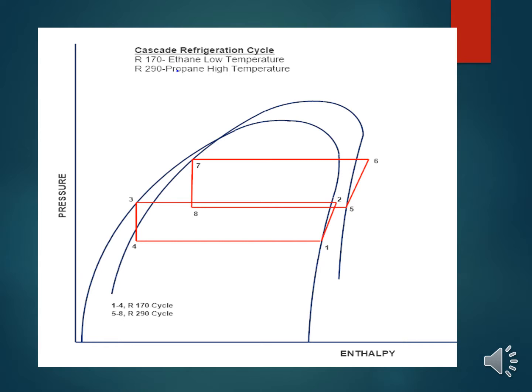This is a pressure versus enthalpy diagram of both refrigeration cycles overlaid upon each other. From point 4 to point 1 represents the evaporating of the R170. From point 1 to point 2 represents the compression of the R170. Point 2 to 3 represents the condensing of the R170 within the interstage heat exchanger. And from point 3 to point 4 represents the expansion of the R170 within the capillary tube.